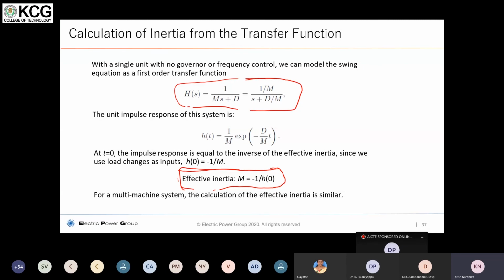The biggest assumption we are making here is that the frequency of your power system will never remain at a steady value of 50 or 60 hertz. This always varies. If you look at 50.002, up to the decimal places, it may remain the same. But if you look at the third, fourth or fifth decimal, it will always change. That means there is always a change in the load imbalance in your system, which can cause this issue, and that is what is essentially taken into consideration in evaluating through this methodology.